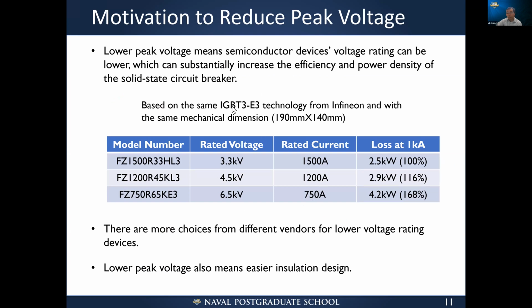In this example, based on similar semiconductor technologies, the same vendors, and the same mechanical dimensions, the only thing we change is the voltage rating, from 3.3 to 4.5 to 6.5 kilovolts. The rated current decreases, and the losses when carrying 1 kiloamp also increase dramatically. So we definitely want to use the lower voltage devices, which means we have to reduce the peak voltages. Other than this difference in performance metrics, there are more choices from different vendors for lower voltage rating devices, which means we have more freedom to choose the devices.